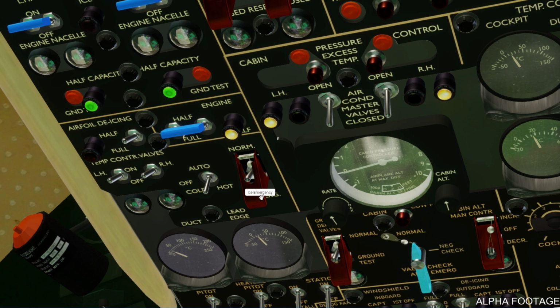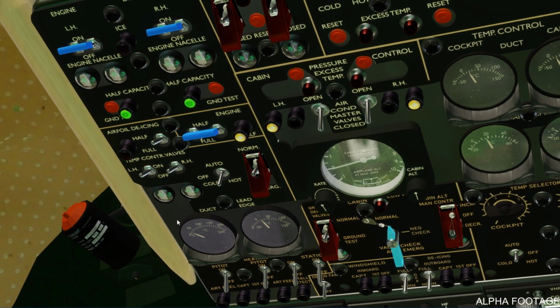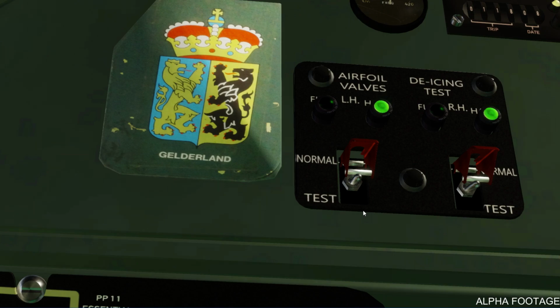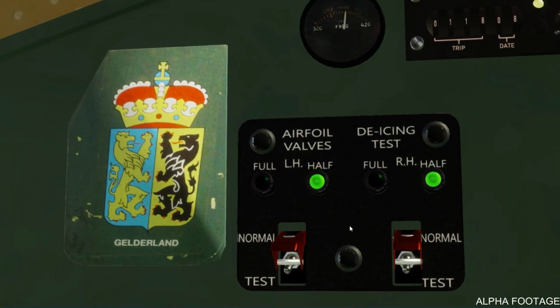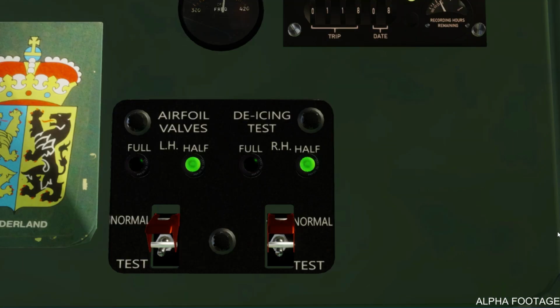Hold the temperature control switch auto manual in the position hot. And now you can see the valves opening. Check the indicator lights marked half. Come on, let's move the camera. Half and half. Set the half capacity switch in the position full.